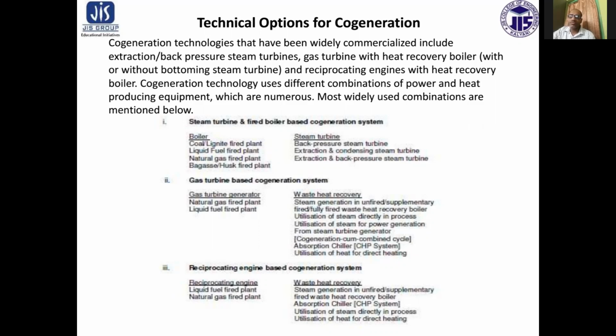That is, first of all, the steam turbine and fired boiler based cogeneration system. The boiler may be a coal or lignite fired plant, a liquid fuel fired plant, a natural gas fired plant, or a bagasse or husk fired plant. The options for the steam turbine are a back pressure steam turbine, an extraction and condensing steam turbine, or an extraction and back pressure steam turbine.